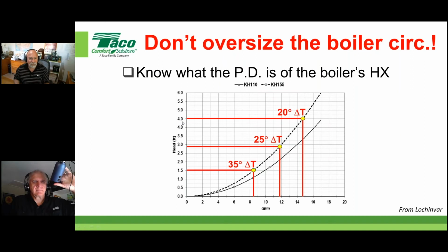Any of these numbers you'll see are relatively small. With this style of heat exchanger, there's really not a lot of pressure drop. But there are plenty of boilers out there that have higher pressure drop. That's okay, because we're talking about very small circulators anyway. There's not really that much of a benefit. So I'm not picking on people that use a different style heat exchanger. I'm just showing you the information I've given you applies to all of them.